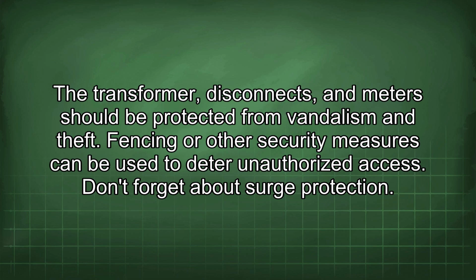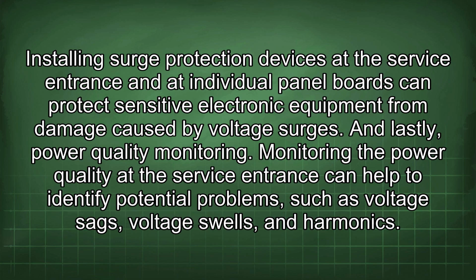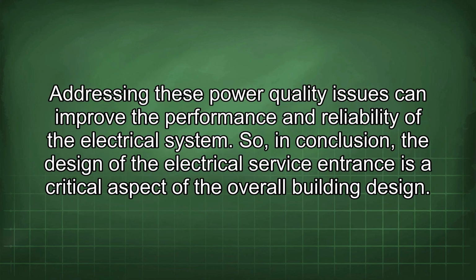Don't forget about surge protection. Installing surge protection devices at the service entrance and at individual panel boards can protect sensitive electronic equipment from damage caused by voltage surges. And lastly, power quality monitoring. Monitoring the power quality at the service entrance can help to identify potential problems such as voltage sags, voltage swells, and harmonics. Addressing these power quality issues can improve the performance and reliability of the electrical system.